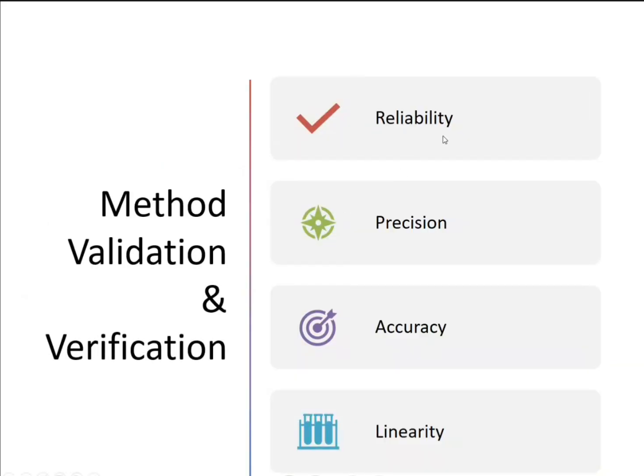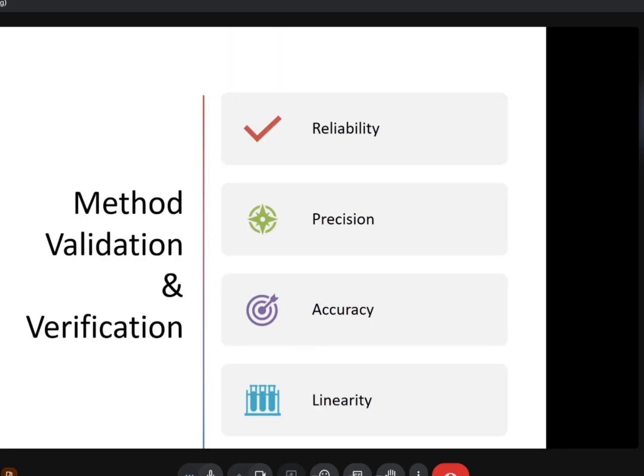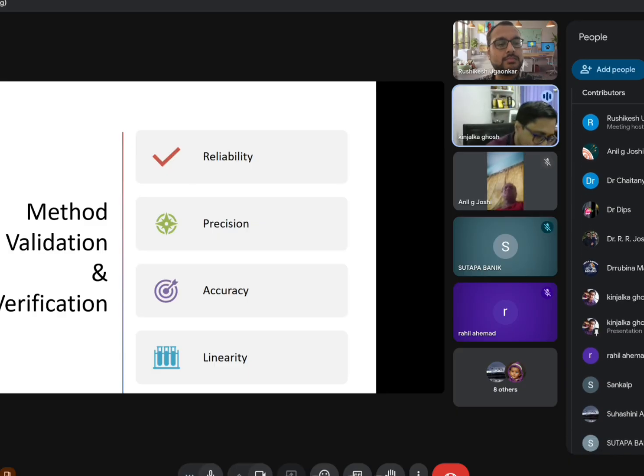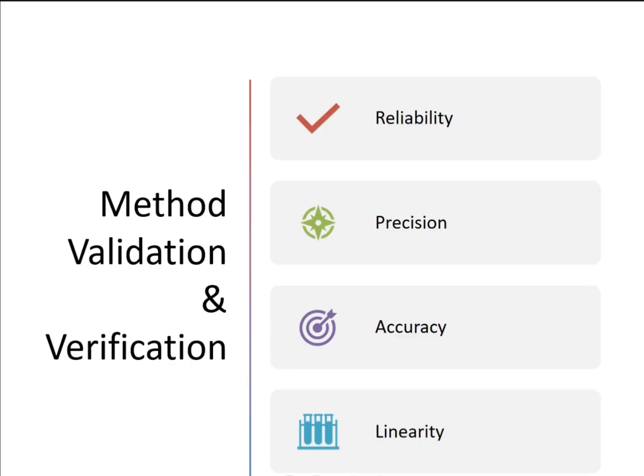So, method validation and verification is necessary because it helps in giving us confidence about the method that we're using, helps with precision or reproducibility, gives us an idea of whether the assay is accurate or less accurate, and also gives us an understanding of linearity. Method validation is something you do when you are repurposing one test for something else. Verification is like a lot to lot verification. A new lot has come and you're comparing the old lot performance with the new lot performance. The QC results you're getting on the old lot may not give you similar results when you're running the same QC on the new lot because there are certain differences, but it should be within range.